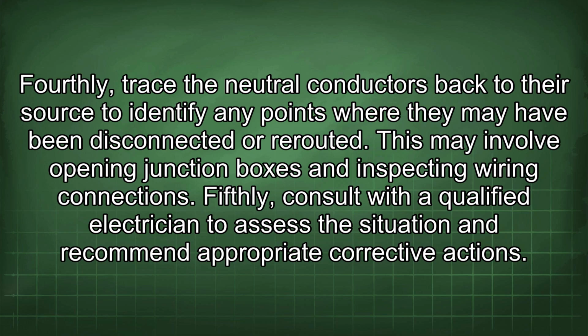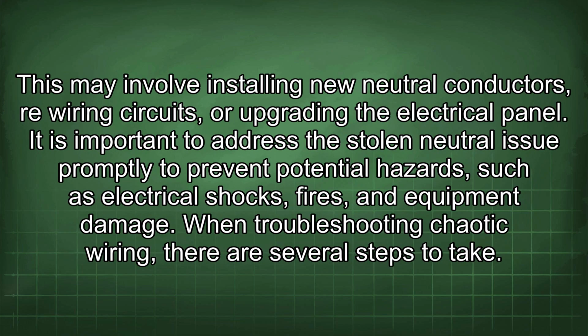Fifthly, consult with a qualified electrician to assess the situation and recommend appropriate corrective actions. This may involve installing new neutral conductors, rewiring circuits, or upgrading the electrical panel. It is important to address the stolen neutral issue promptly to prevent potential hazards such as electrical shocks, fires, and equipment damage. When troubleshooting chaotic wiring, there are several steps to take.